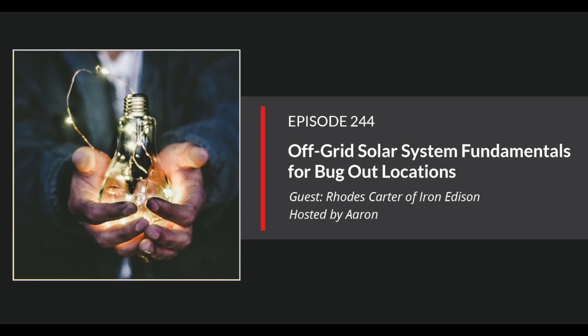So once we have those two numbers, let's start looking at the battery. Just for nice round numbers, let's say our home uses the national average energy consumption for a single-family home in the US, 30 kilowatt hours a day. The next question: how much time of autonomy do we want? Basically, how long does that battery need to last before it has to be recharged? There are different schools of thought on this, anywhere from 1 day, or 24 hours, of autonomy, to some people who want 3 or 4 days of autonomy. So you could have a 30 kilowatt hour battery up to a 120 kilowatt hour battery.